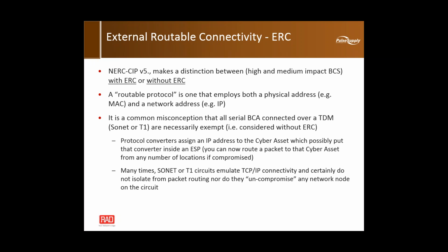It's a common misconception, and NERC warns power utilities that just because a cyber asset is connected over a TDM network, whether SONET or T1, it isn't necessarily exempt from electronic or external routable connectivity. If you're using protocol converters, they could have IP addresses, and even though they're transported over a TDM network, there's still an IP address assigned that can be accessed remotely, and you could spoof it, turn it off, or change its settings. So it has to be protected, and it falls under this external routable connectivity rule.